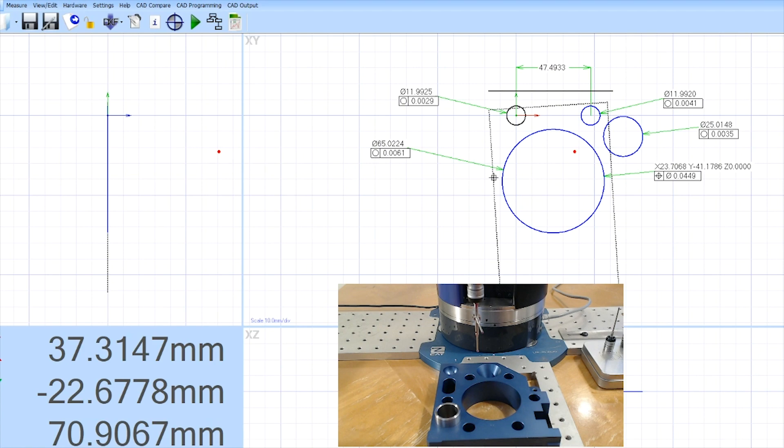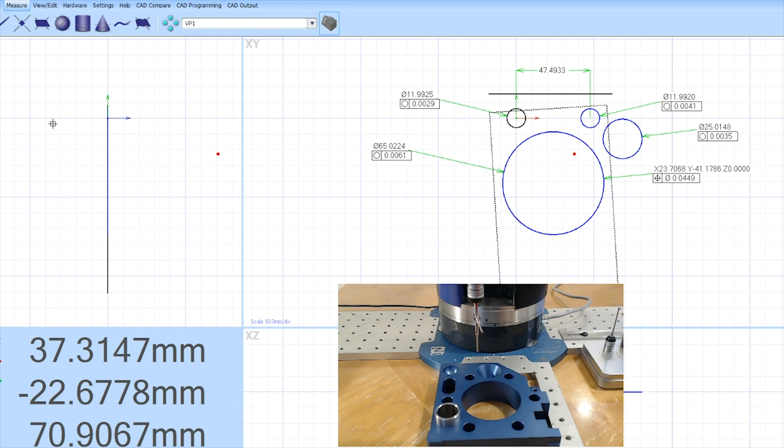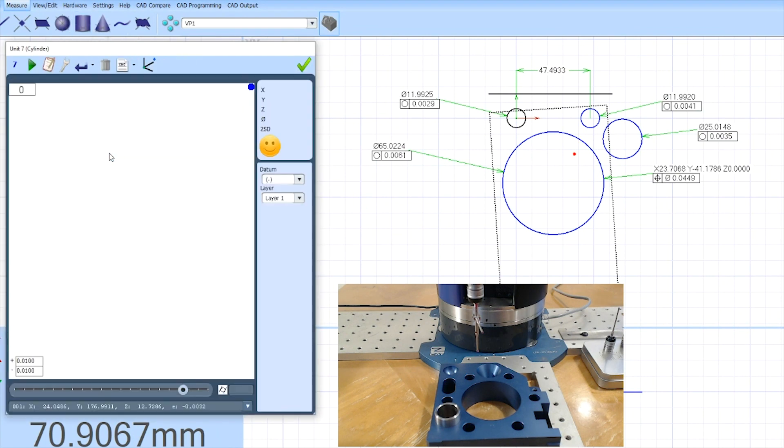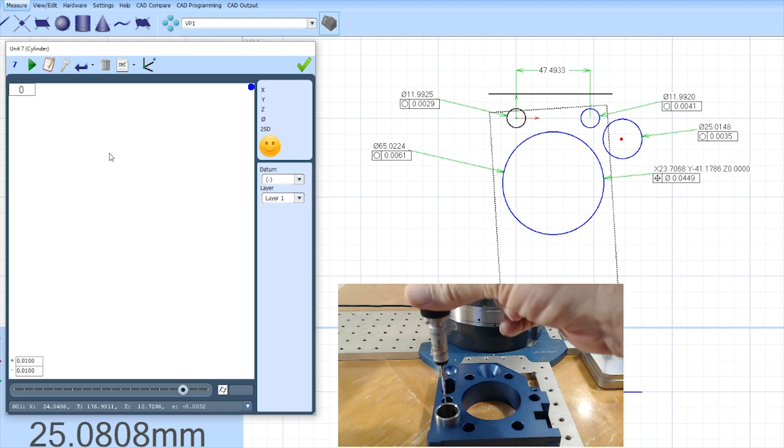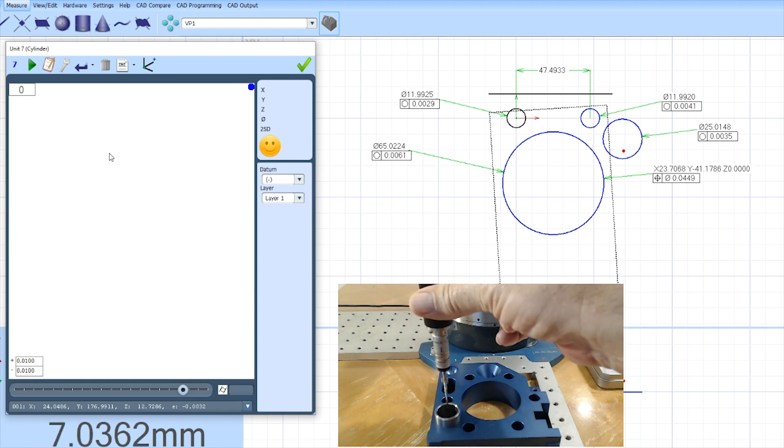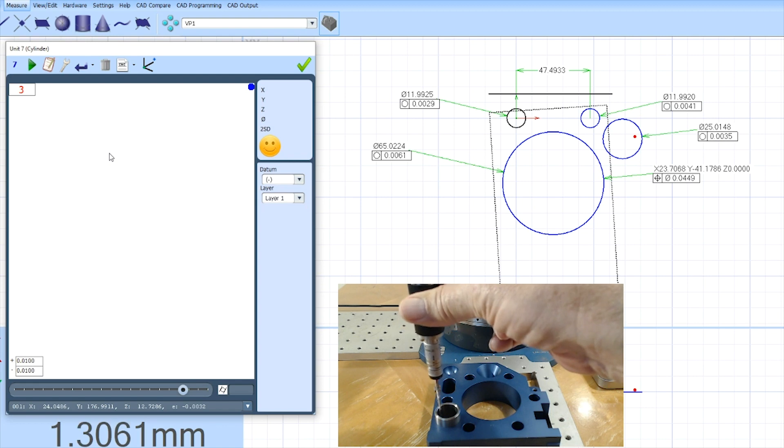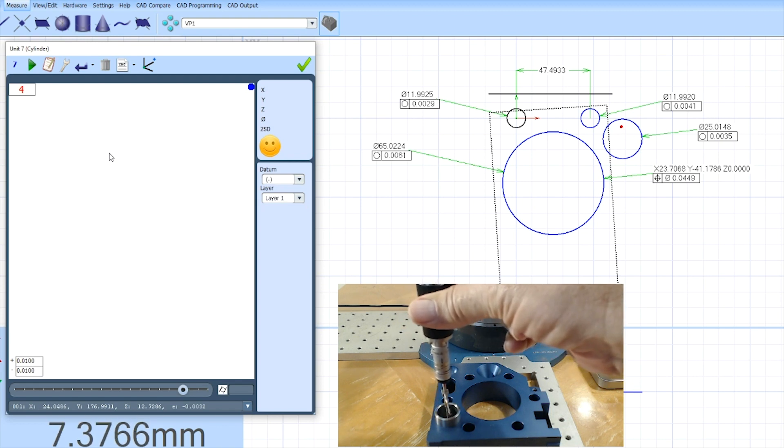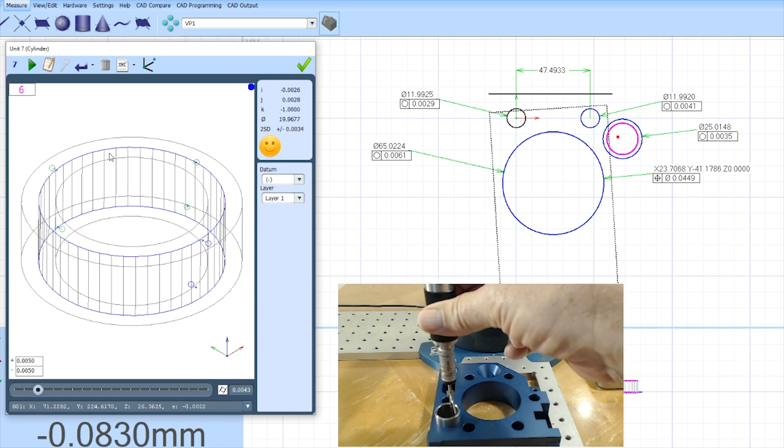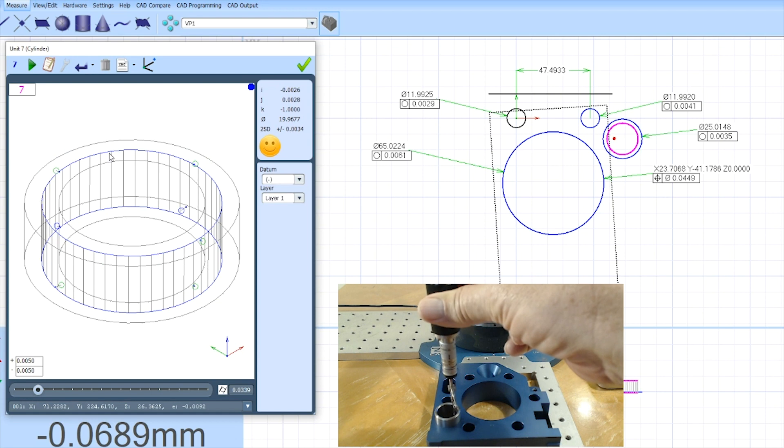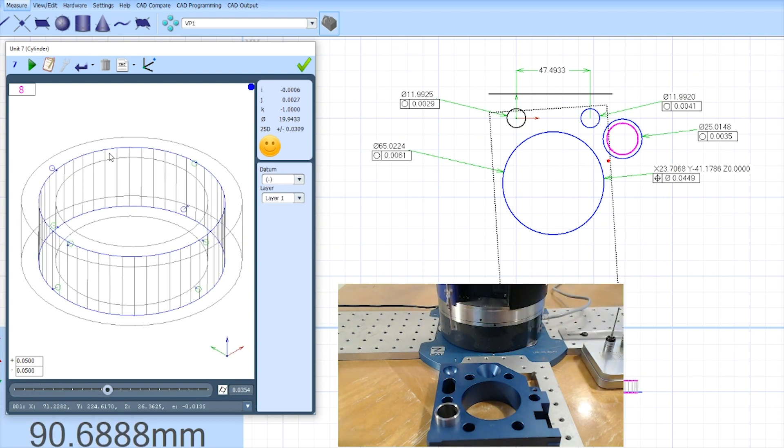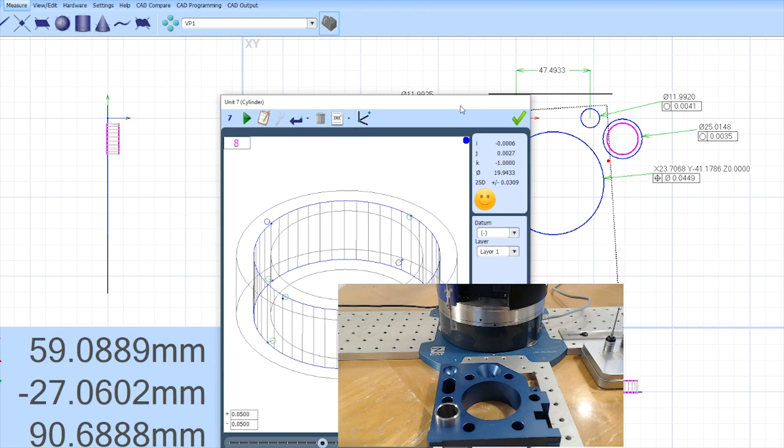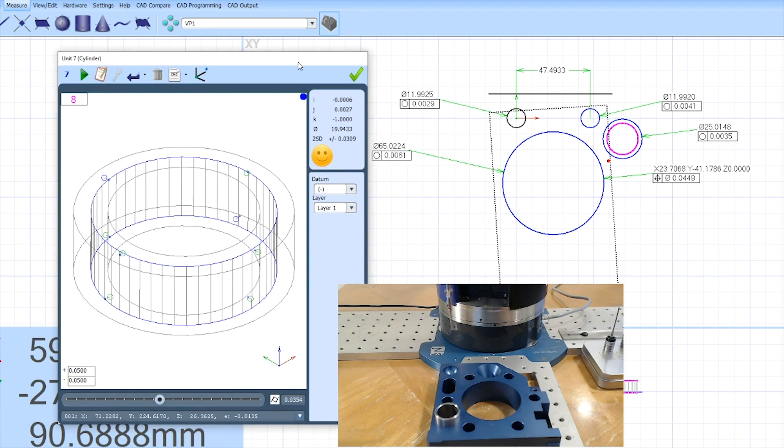I've already measured quite a few features but I can choose some other features. Let's say I want to measure a cylinder. It will not predict a cylinder so I have to tell it ahead of time I'm going to measure a cylinder. So I'm going into this cylinder right here and start taking random points inside the cylinder. And you can see there's my cylinder. It's now going to start showing in my X, Z window and my Y, Z window in more in 3D.